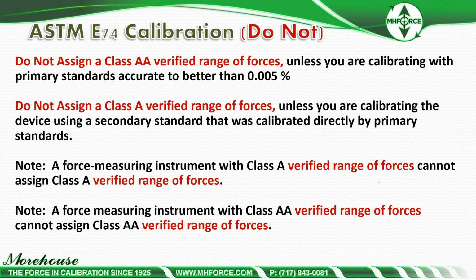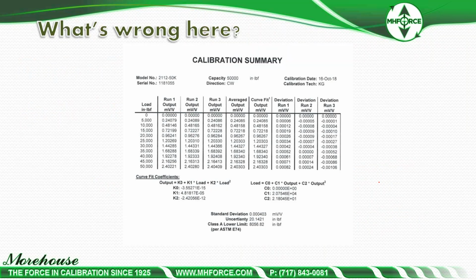Other things: do not assign a Class AA verified range of forces unless you're calibrating with primary standards accurate to better than 50 parts per million. Do not assign a Class A verified range of forces unless you're calibrating the device using a secondary standard that was calibrated by primary standards. So you need a Class AA. Your certificate absolutely has to say Class AA verified range of forces for you to calibrate other load cells in accordance with ASTM E74. So a force measuring instrument with a Class A verified range of forces cannot assign a Class A verified range of forces. A force measuring instrument with Class AA cannot assign Class AA.